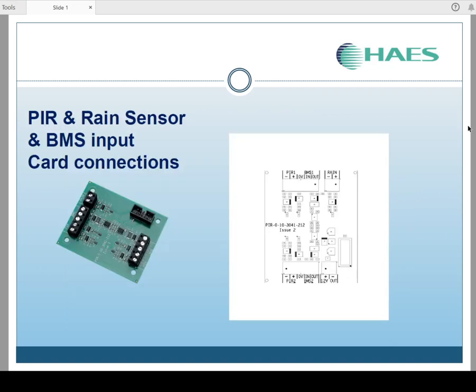This is a picture of the plug-in card that gives us our PIR, rain sensor and BMS inputs. For this single zone panel, we'll be just using the top row of connectors, which is the PIR1 pos and neg inputs for your PIR. You've then got your BMS inputs for your 0 to 10 volt inputs from your BMS system, your rain pos and neg terminals for your rain sensor, and at the bottom there, the 12 volt pos and neg terminals will be fitted so that you can supply the PIR. The PIR2 and BMS2 inputs will not be fitted for this panel.